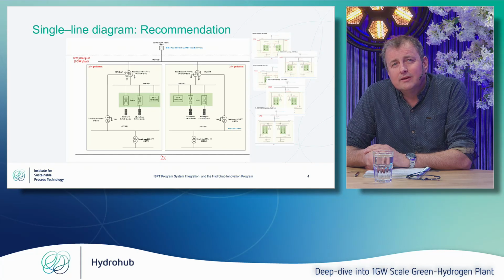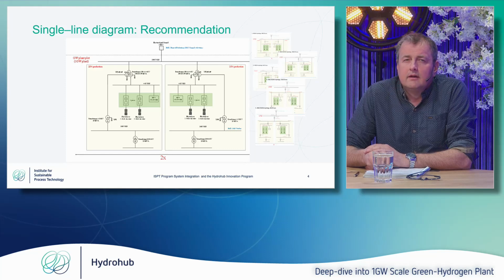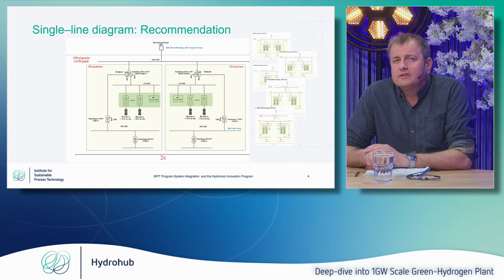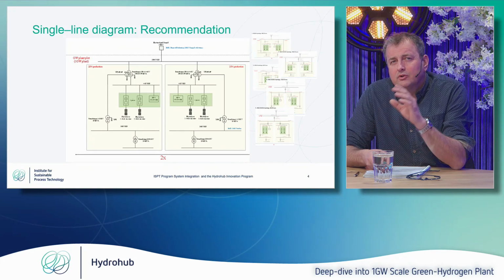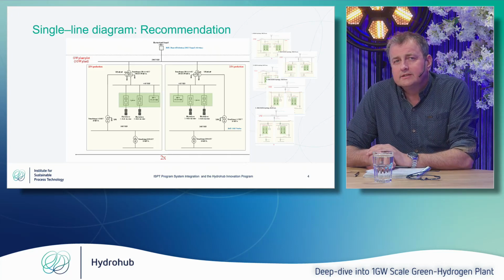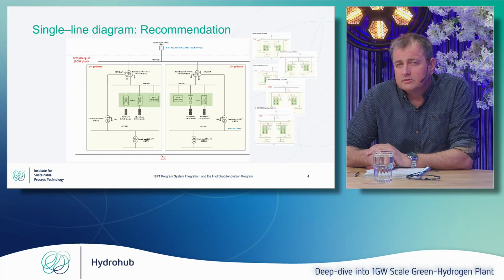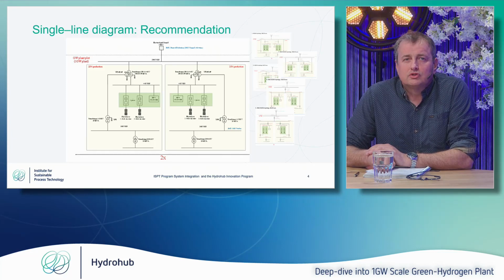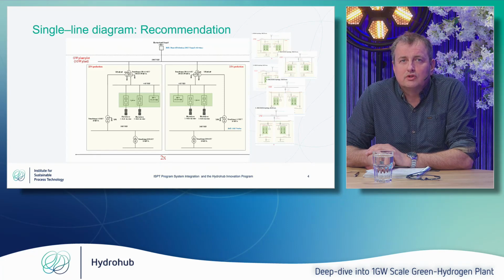One of the things we also discussed is the balance of plant, so basically all the other consumers needed for the electrolyzer plant. We try to disconnect them from the electrolyzer part because the electrolyzers cause the harmonics and the disturbances in the grid. You really do not want those disturbances at your other consumers because that will cause problems. That's why we have chosen a three-winding transformer, where the third winding goes to the balance of plant.